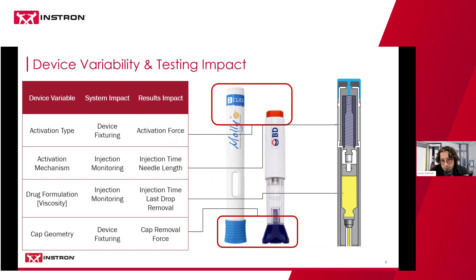And that obviously means we would need a way to interact with every cap that comes on the market in a way that is not difficult to change out on the system. And obviously, the different cap styles will impact how we fixture it, which will in turn impact the cap removal force that you would measure. So, this is just to highlight the impact that all of this variability can bring. And this sets the stage for the challenges we had to work through to make the system as robust as possible.